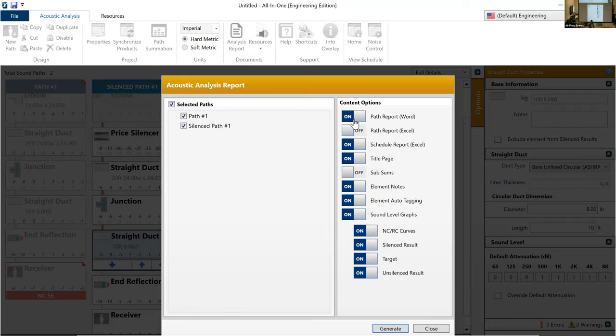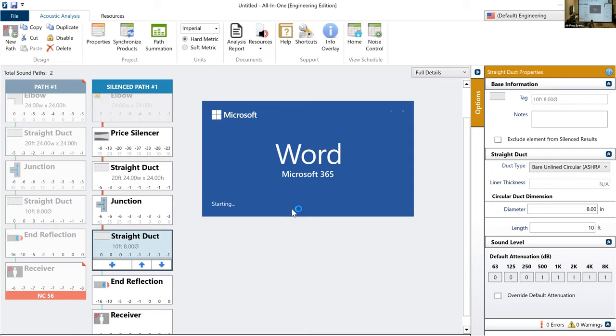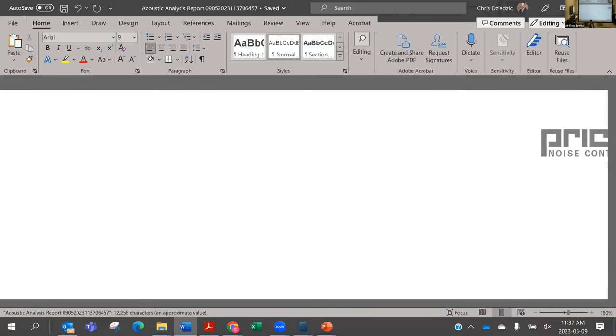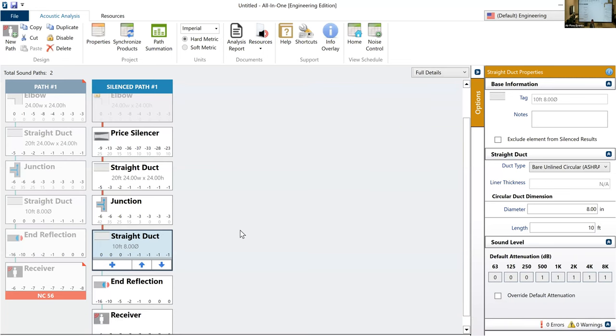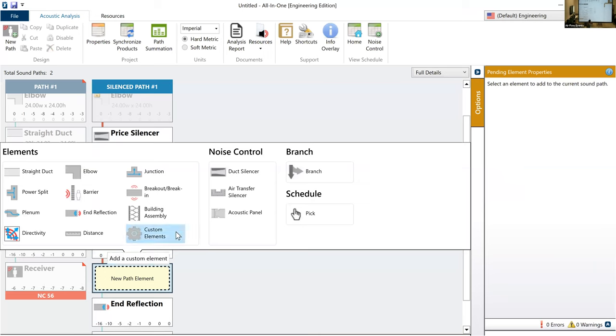That's one thing that's really not in there, is VAV boxes. They're not really a sound generator, but they are. So there's a project we're working on behind the scenes to see if we can grow this tool to include all price products or any manufacturer's products. Right now, in the middle section, it has noise control products. Well, what if you wanted fan coils or blower coils or fan power terminal boxes or diffusers or whatever? We're looking at how you could do that. Part of the problem is that for the program to work accurately, you need all 8 octave bands of sound level. A lot of VAV boxes only use bands 2 through 7. They don't use 1 and 8. So you're left with some missing points.